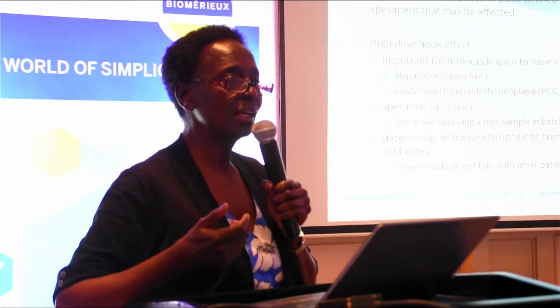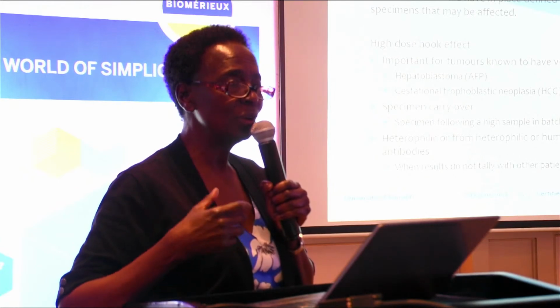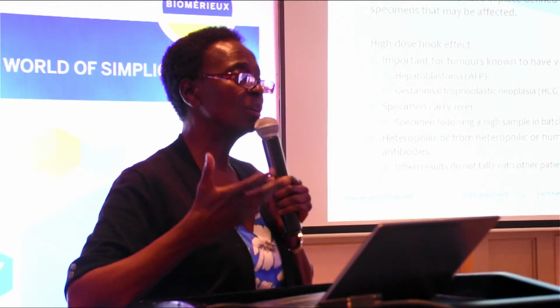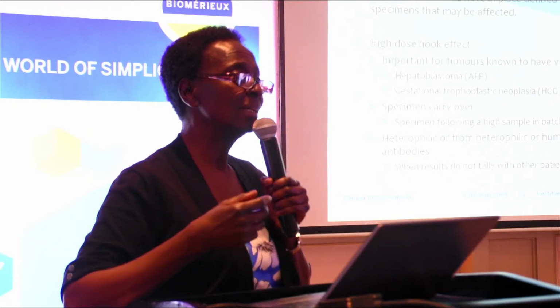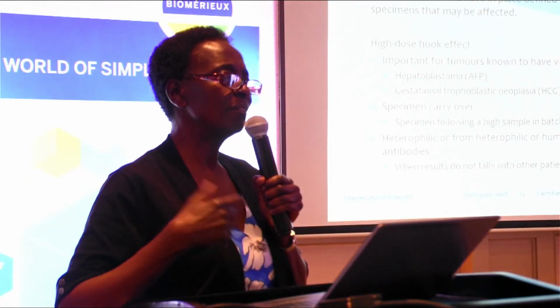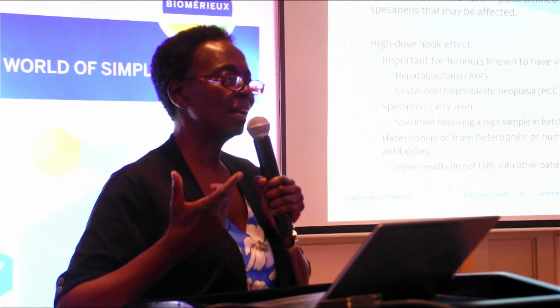Specimen carryover can also occur, especially for labs which do batch analysis. I think most of us do random access, so it is unlikely that one patient sample will follow the other, but when there is batch analysis, that can happen. So if a sample follows a very high result, you may have carryover.